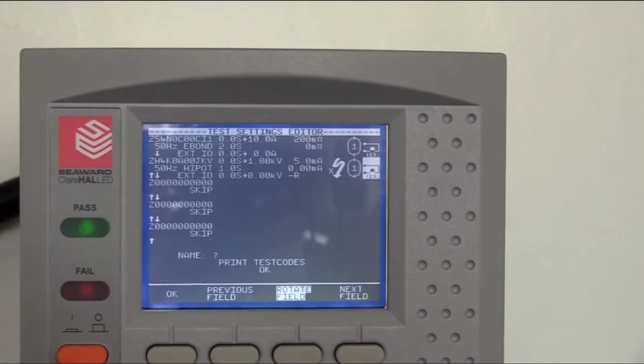So once we've completed that, that now gives us the full safety requirements as prescribed by the standard. But as an additional test and as an additional quality measure, we may want to perform a functional test. That functional test allows us to be sure that the product under test not only is electrically safe, but also functioning as we would expect. So we're going to select the test. In this case, we're going to do what's called a power and leakage test.